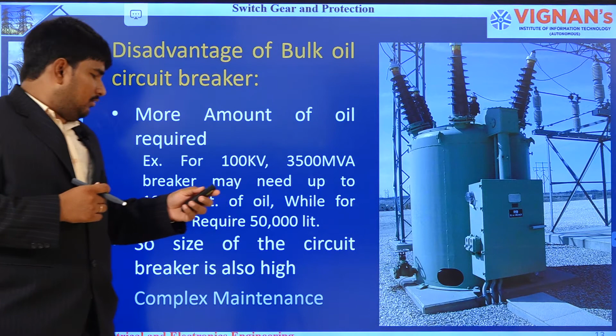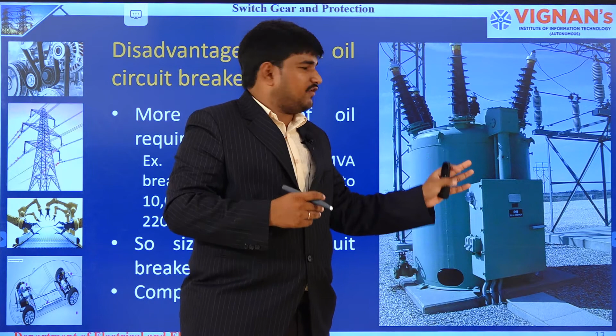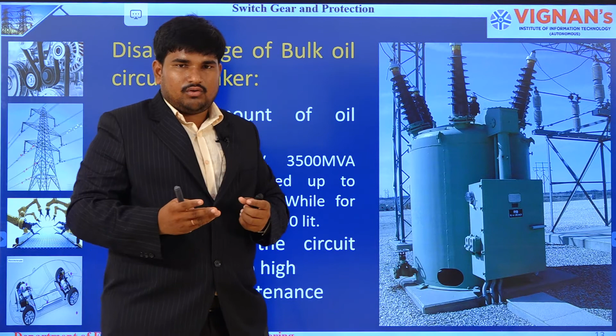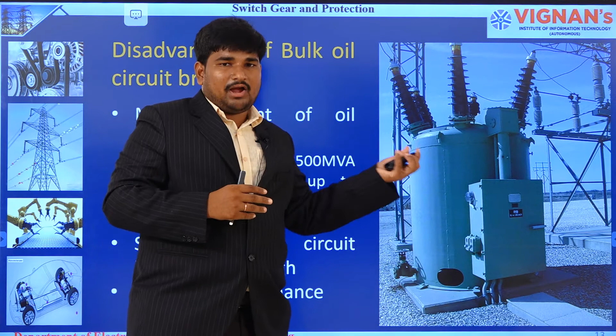So that is the disadvantage of bulk oil circuit breaker. The next disadvantage is, for example, if you want to do maintenance here, what do we need to do? First we need to take out the entire oil, which is 10,000 or 50,000 liters, from the tank. Then only we can maintain. So this is very costly maintenance and also very complex maintenance. This is one more disadvantage in case of bulk oil circuit breaker. To avoid that, we went for the minimum oil circuit breaker.